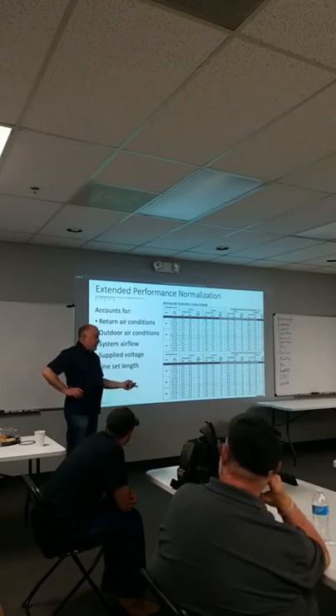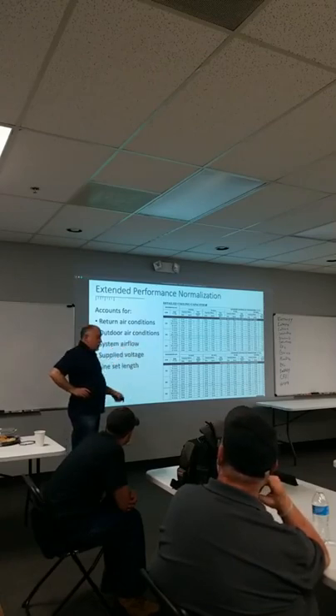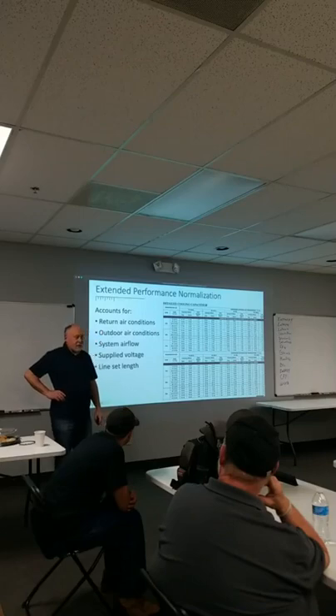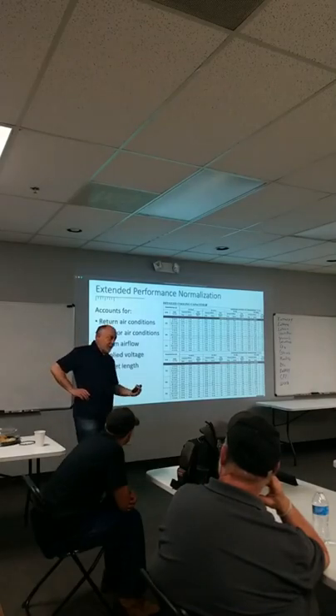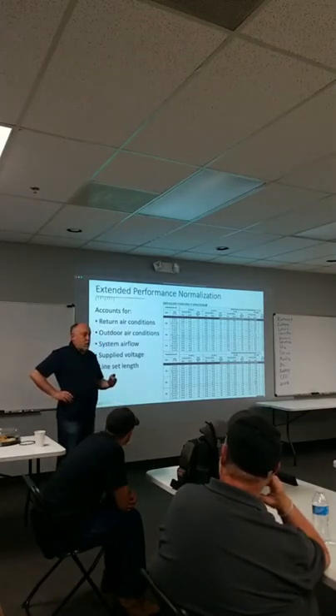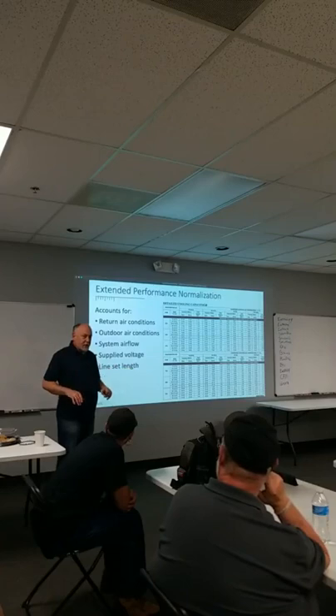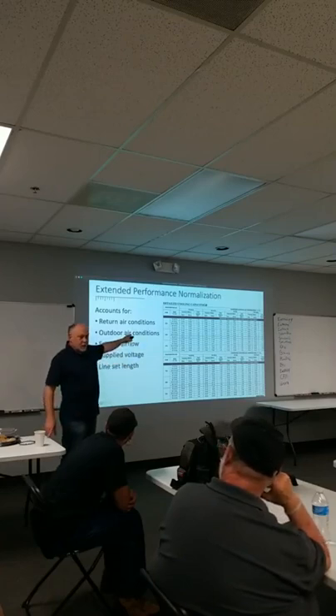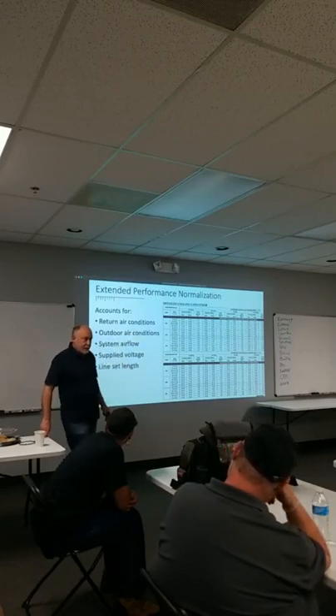Now, this chart, though, doesn't take into account some other variables that affect capacity, which we do in Measurequick. Like, do you have 208, 230, or 240 volt? Anybody know what all equipment is actually AHRI rated at? There's a specified voltage for all equipment. Anybody know what it is? 230? 230, there you go.